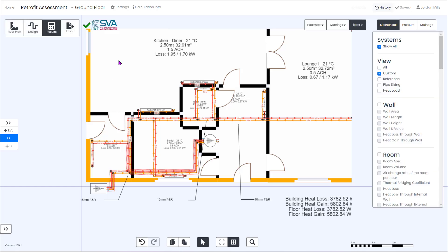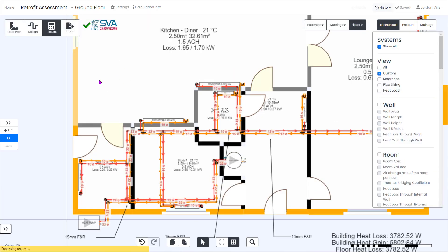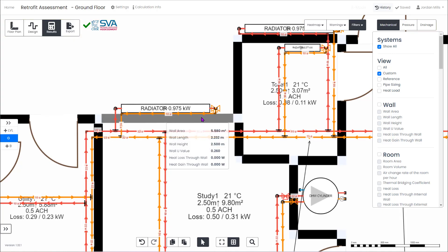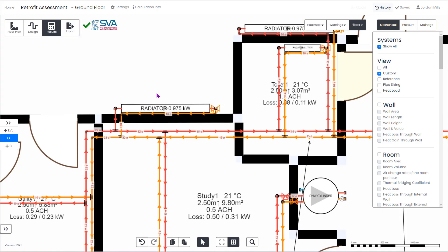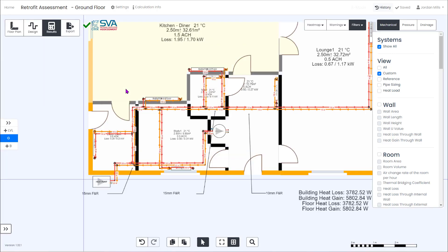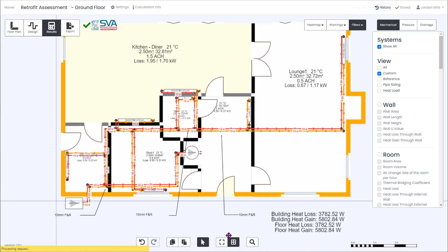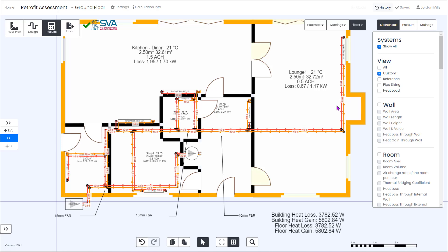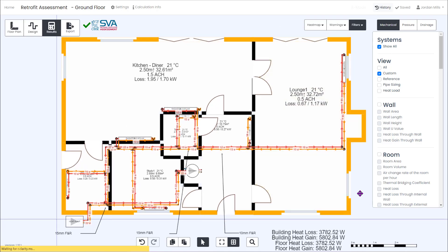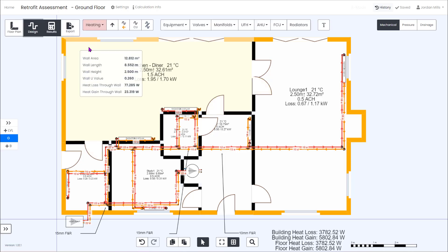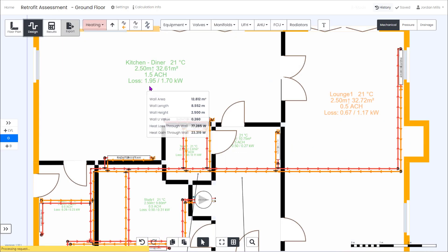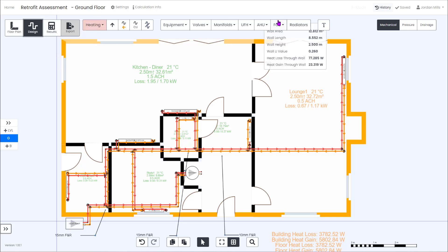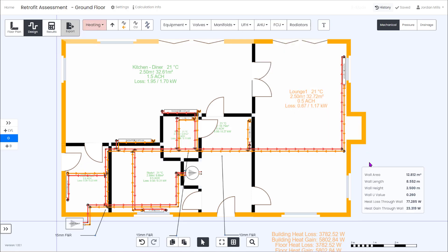At this point we can rerun the results and there's quite a bit to dive into. Firstly we can see that our 10 mil pipes to each radiator are still adequate which is great. Looking at the room by room heat loss, although the outputs have gone down a lot, the kitchen diner has gone from 4.4 to 1.95, they are all still green other than the lounge where we will need to add one extra radiator.